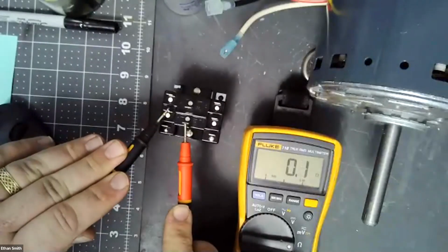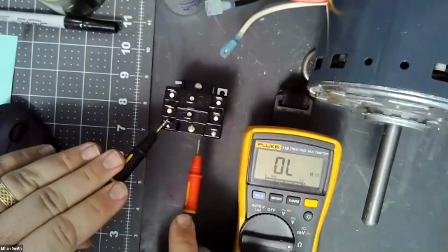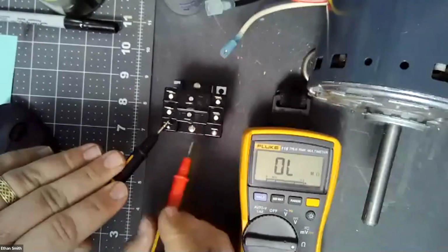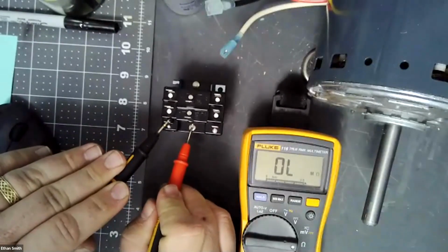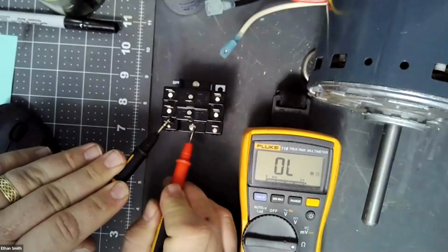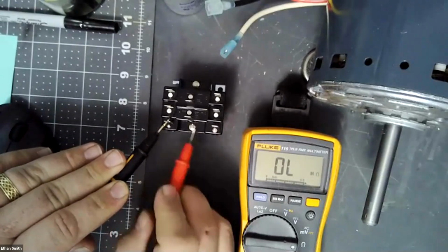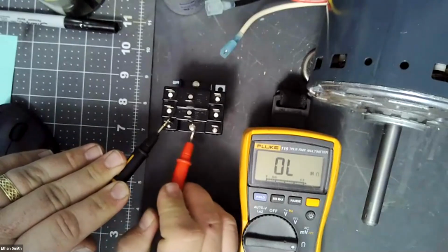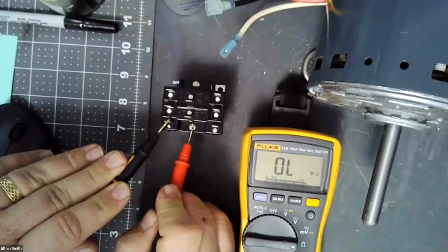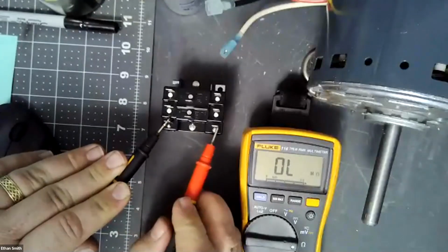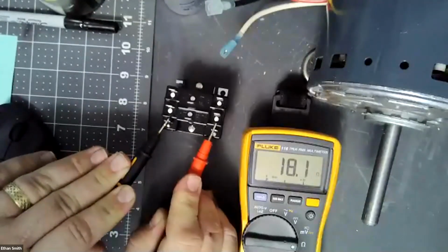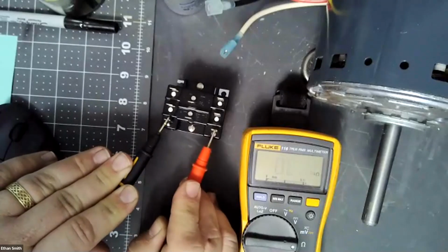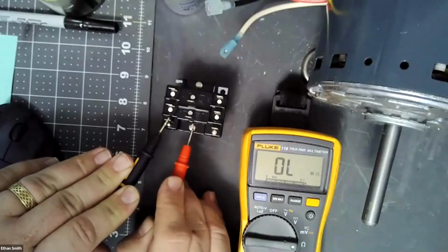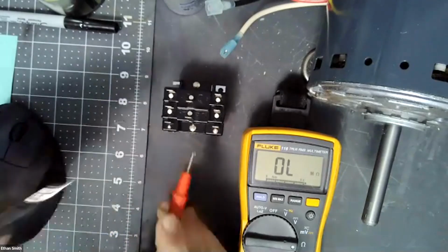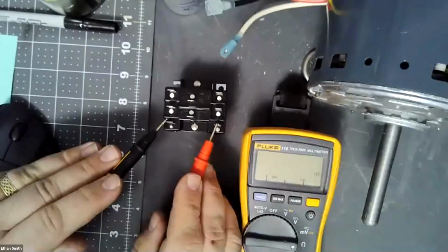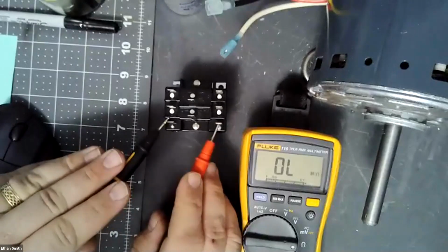Conversely, if you were to get onto a coil and you were to notice that it gave you almost no resistance, or if you were to take a coil to a ground position, so this is a grounding terminal right here, if we had continuity there and a resistance reading, we would know that this coil in here has shorted to ground. Typically, you're going to see popped fuses if you see that kind of thing. But this one, we've got just our coil resistance right there, 18 ohms. So we know that we have a coil. We know it's intact. We've got no continuity to ground. Okay, and it's not OL and it's not a dead short. So we know that this coil is probably okay.